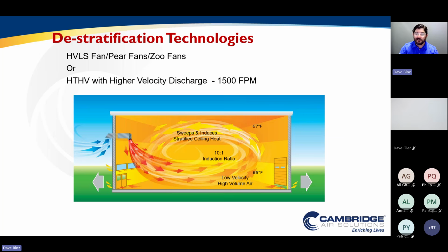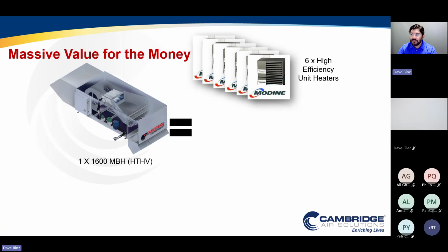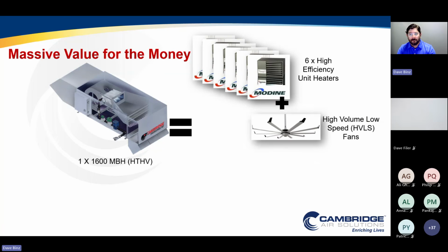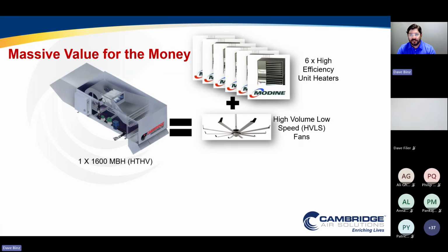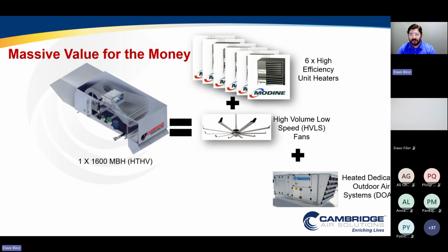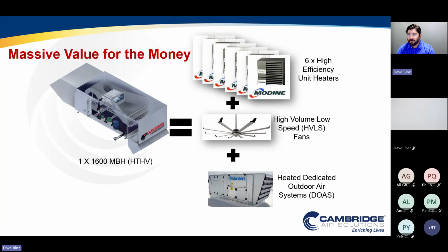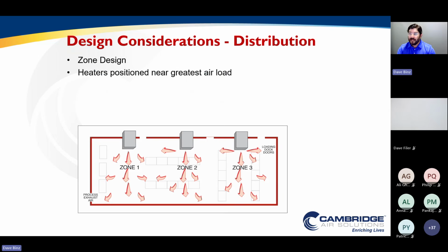These can be used in conjunction with HVLS fans, or in many cases, in the absence of HVLS fans. So when I'm retrofitting an existing warehouse space, my single unit can provide the same effects as 6 high-efficiency unit heaters, distribution technology like HVLS, and also some tempered ventilation, to meet my ventilation, distribution, dehumidification, and space heating needs. Now, in one package where I'm trying to minimize equipment in the space, minimize distribution, and lower my install costs along with my operating costs, we have a really unique package. This technology is a really unique package for that.